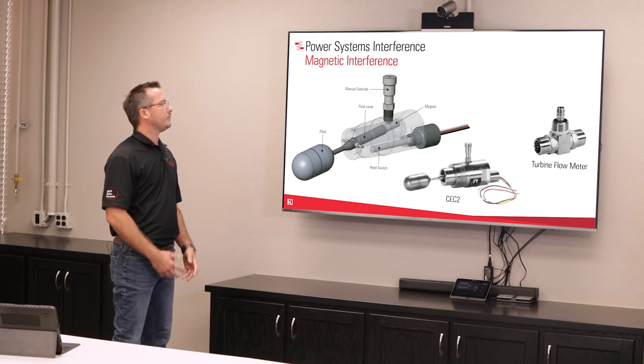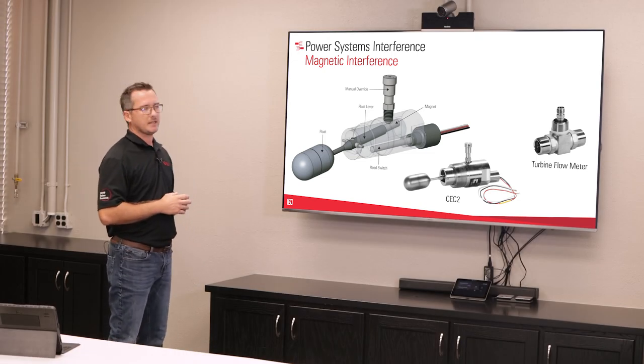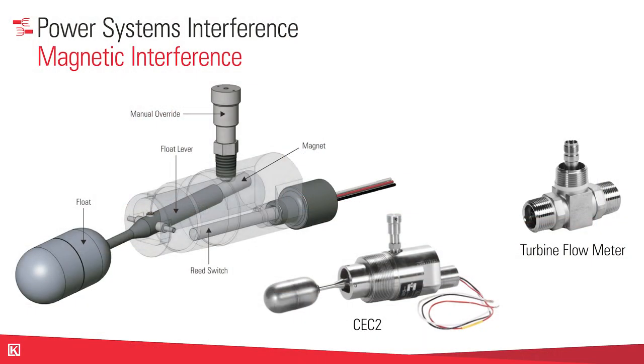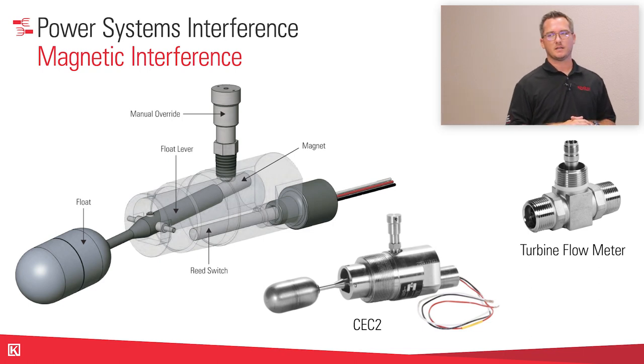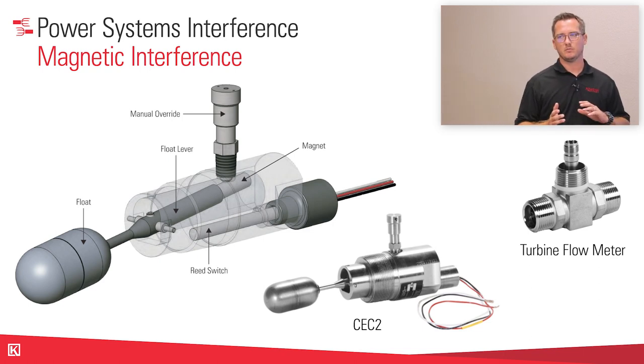Another big interference other than static electricity is magnetic interference. We've got a couple products that use magnets, whether that's the CEC2 level controller with the magnetic switch, or the Badger meter systems that we use that uses the turbine and the magnet to have a pickup. So you can get natural magnetic interference in the area with the moving liquid. You've got liquid moving at a fast pace in a metal system. The ground and the bonding systems aren't tied together, and you're going to pick up a magnetic interference.